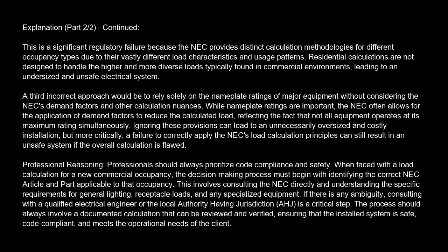A third incorrect approach would be to rely solely on the nameplate ratings of major equipment, without considering the NEC's demand factors and other calculation nuances. While nameplate ratings are important, the NEC often allows for the application of demand factors to reduce the calculated load, reflecting the fact that not all equipment operates at its maximum rating simultaneously. Ignoring these provisions can lead to an unnecessarily oversized and costly installation, but more critically, a failure to correctly apply the NEC's load calculation principles can still result in an unsafe system if the overall calculation is flawed.